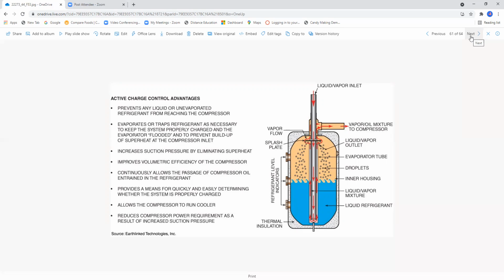It continuously allows the passage of compressor oil entrained in the refrigerant. It provides a means for quickly and easily determining whether the system is properly charged. It allows the compressor to run cooler. It reduces the compressor power requirement as a result of increased suction pressure.